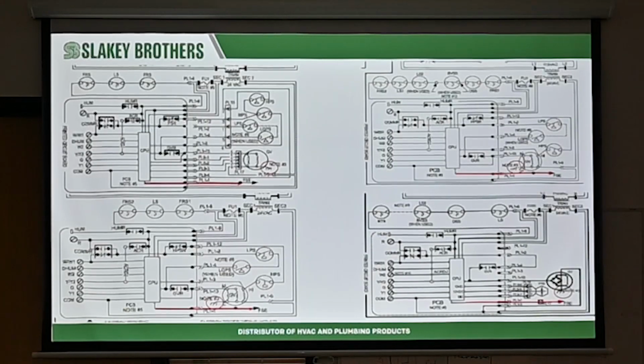But if your switch shows continuity, but your board is still registering a faulty pressure switch, you've got to watch your wiring. So let's look at a simple one like this here. You've got power going to the low pressure switch, and back here to this connection point. There is no low gas pressure switch in this scenario. But then for your high pressure switch, it goes to the gas valve, to the pressure switch, back to the board. Just reconfirm that there's nothing wrong with the wiring.